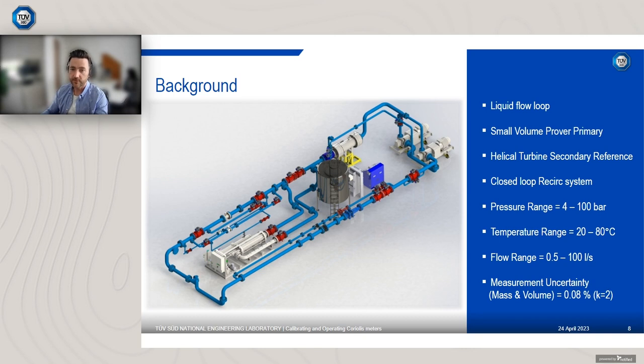You can see we've got two main recirculation pumps and an in-line heat exchanger. The fluid then flows through that, through our primary reference system, which is a small volume prover. That's the white equipment you can see in the lower left-hand corner. That's known as a small volume prover. It's a 60-litre Emerson compact prover. It's now a Brooks prover since they got acquired by Brooks, and it has a measurement uncertainty of 0.08% as our primary, the way that we operate.